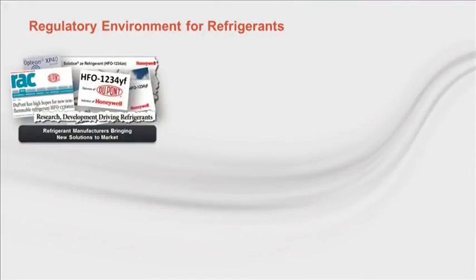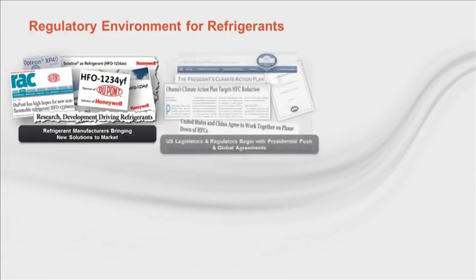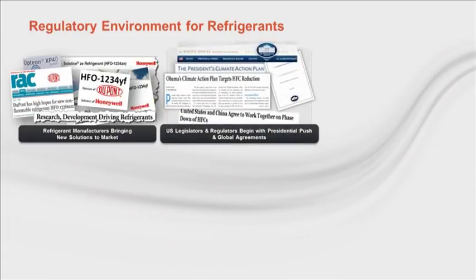With the recent proliferation of low GWP alternatives offered by the chemical companies, countries have been moving rapidly to take advantage of these new refrigerants. In the United States, the current administration has developed a climate action plan that targets HFC reduction, among other actions, and the Environmental Protection Agency has adopted new regulations through the Significant New Alternative Program, or SNAP, to institute these goals. For example, a proposed rule change by the EPA would delist R507A and R404A as acceptable refrigerants for new and retrofit retail food refrigeration beginning in 2016. Likewise, R134A would also be delisted under the same proposed rule for new standalone retail food refrigeration and new vending machines.